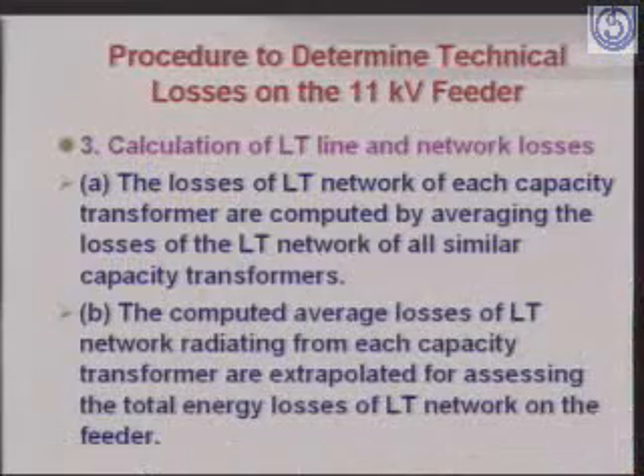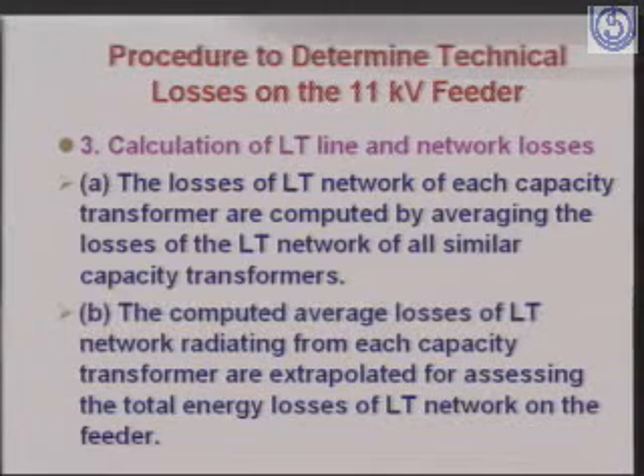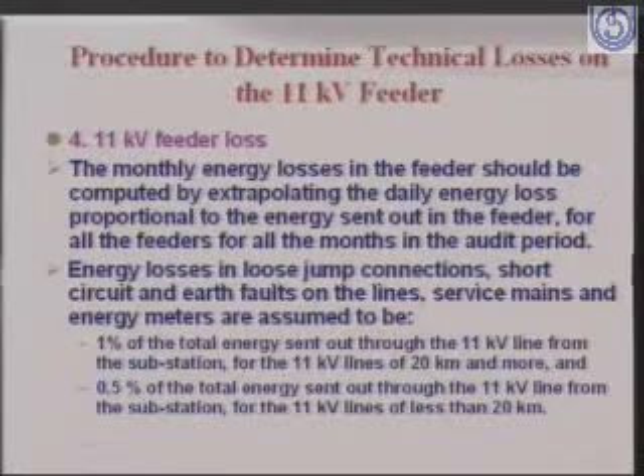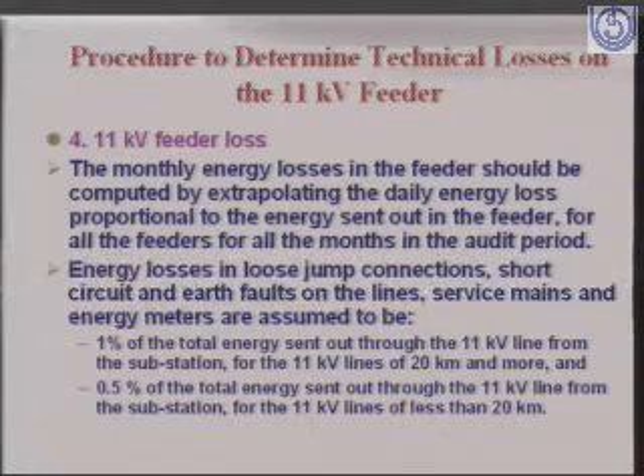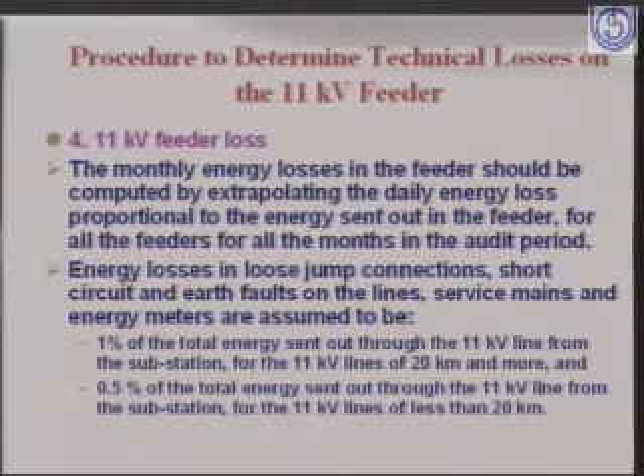Calculation of LT line and network losses after the transformer. We have the LT network, and the procedure mentioned in your books is basically a rough estimate through which we can identify the LT line and network losses. And when you combine all this, then we are in a position to find out the total 11 kV feeder loss. So the monthly energy losses in the feeder should be computed by extrapolating the daily energy loss proportional to the energy sent out in the feeder, for all the feeders, for all the months in the audit report.